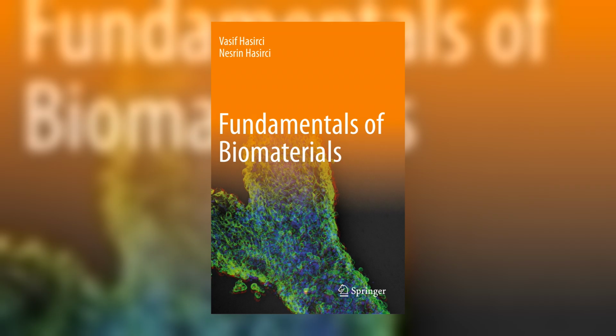This is one slot in the 10993 series, which partitions biocompatibility by dissolution chemistry rather than device shape. Ceramics get Part 14. Metals and alloys get Part 15. Polymers get their own. Predict the pattern from there. Every material class earns a degradation product module because you assay the leachate.